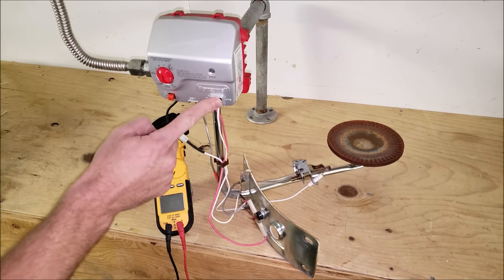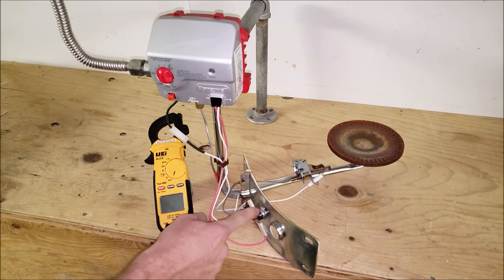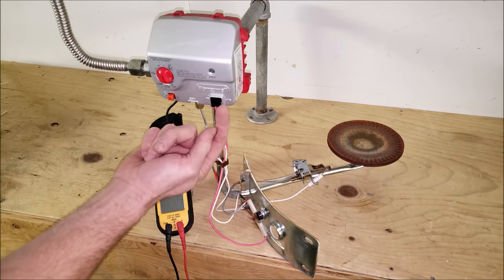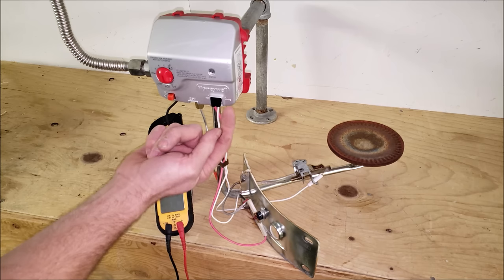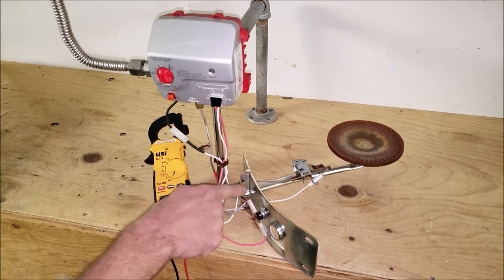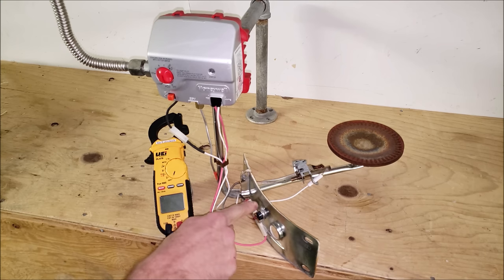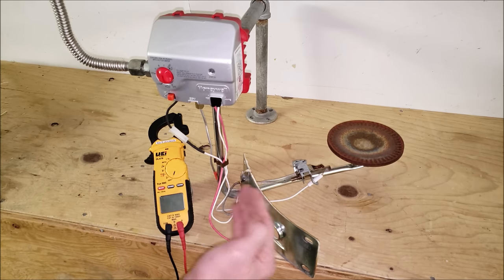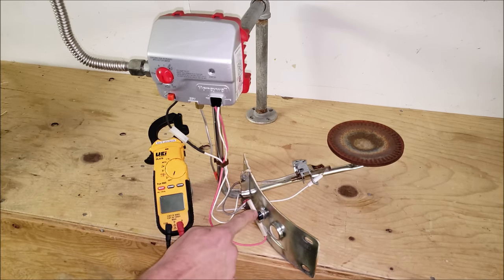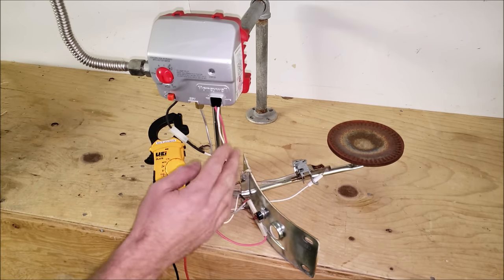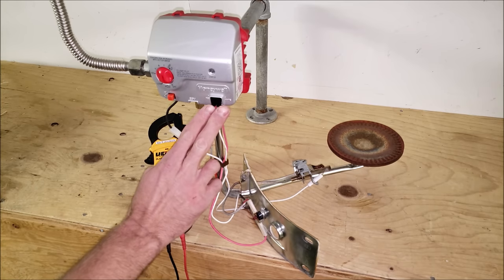We could also have a problem inside this thermo disk. This is a red wire here so you can put a multimeter on the white negative wire and then one over here and then afterwards you can take another reading over here and see if you have a voltage drop across this indicating that there is a resistance. You're only going to have a very small amount of voltage drop across this. But doing your initial check on this I would typically go ahead and put my probes right in here.